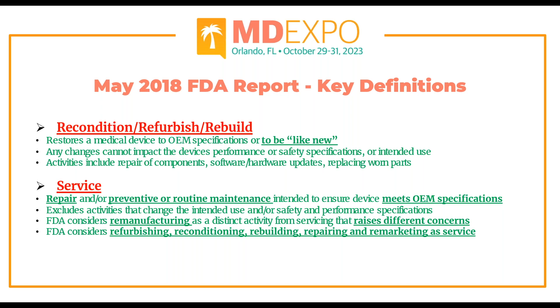Again, FDA considers remanufacturing as a distinct activity from servicing. So remanufacturing is completely different from the servicing piece, and it raises different concerns. So the FDA considers refurbishing, reconditioning, rebuilding, repairing, and remarketing as service. Remanufacturing carries manufacturer's requirements. More key definitions: repair, a type of servicing; remanufacture. Again, they are saying that these activities significantly change the device performance.